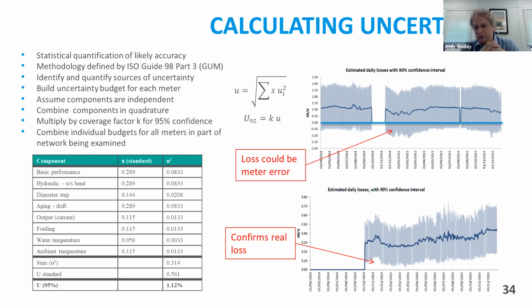Again, we've taken off all the outputs from the input, more than one input in this case, looked at all the uncertainties, and mapped those uncertainties onto that residual, that dark blue line, which is potentially leakage. We can see that there, even allowing for meter uncertainty, there is still a residual. That band defined by the uncertainty bands never goes down to absolutely zero, which suggests there is a real loss in that network somewhere.